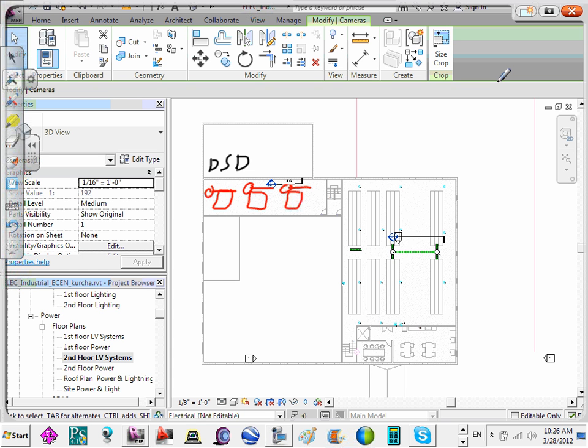So we've got our duct smoke detectors on the air handling units. Those are going to come in as a supervisory alarm. They're not alarms anymore. They're just going to shut down the units in case there's smoke, so it prevents them from recirculating smoke throughout the building. The reason that they're supervisory is because really by the time the smoke gets there, you're either going to have a real smoke detector or sprinklers going off, or they're just faulty and there's dust or something. So they don't want the fire trucks rolling every time. We hear that all the time. So these are going to report as supervisory.